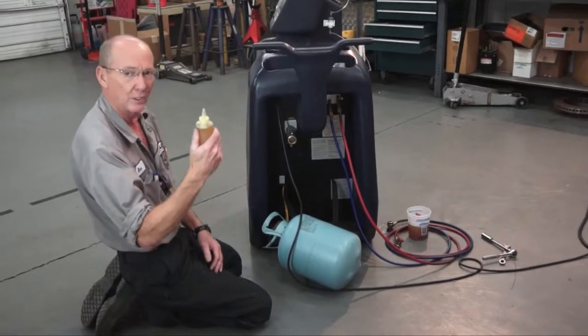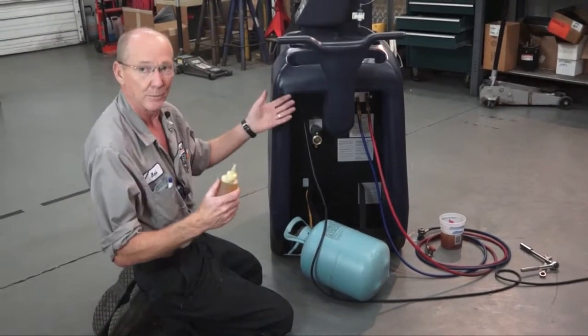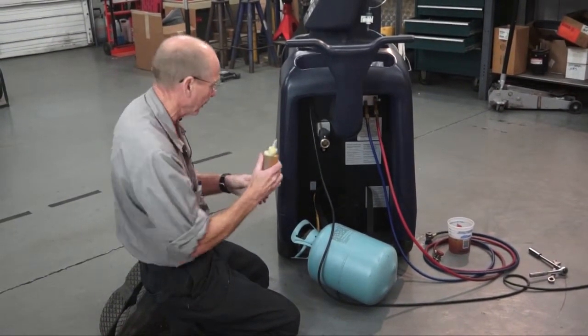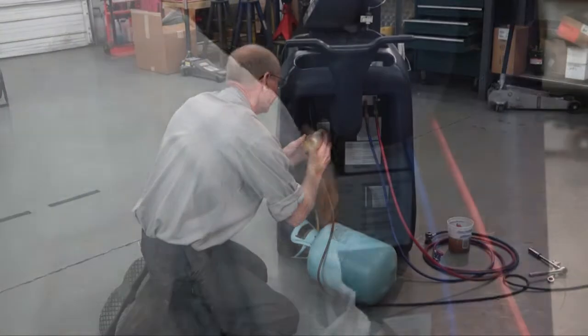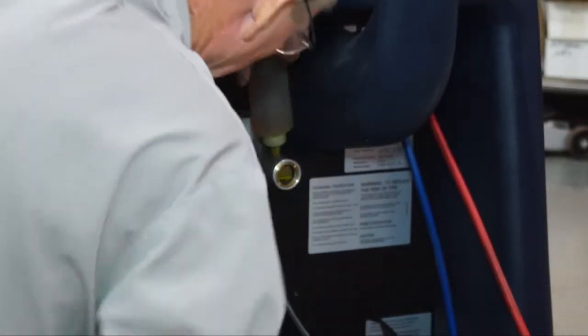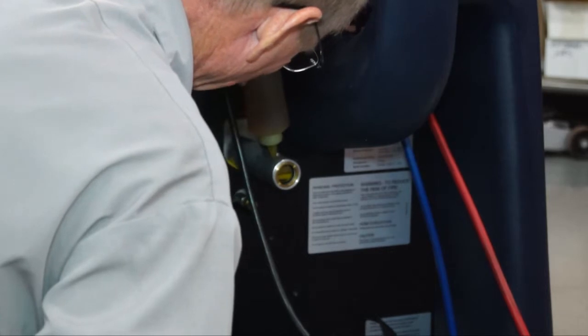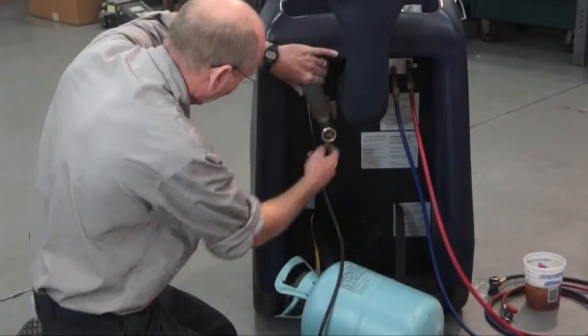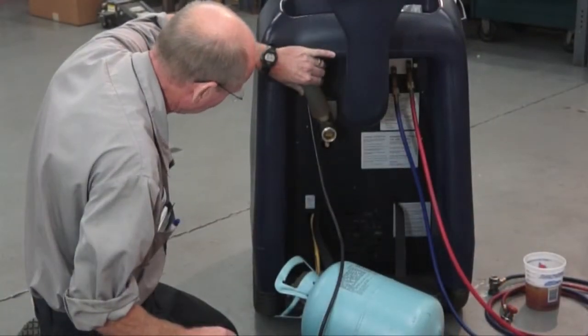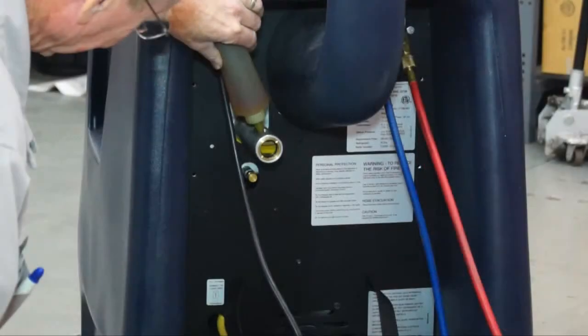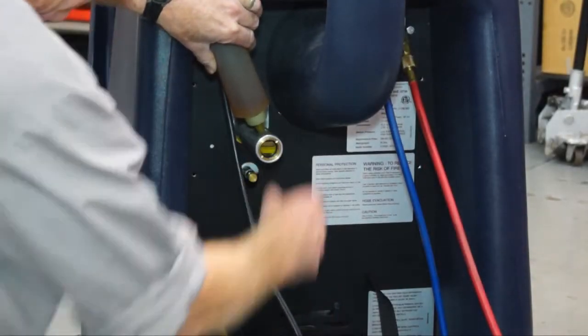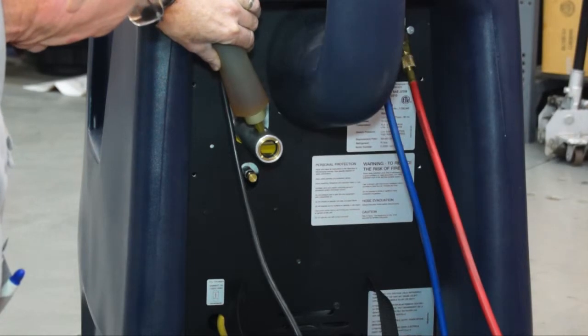And I'll get this full 8 ounce bottle, and I'm not going to run the vacuum pump because there's basically no oil in it, very little oil. So I'm going to squeeze it in just a little at a time. You can watch the sight glass, that way you know you're not going to overflow back out of the hole. But it takes a little bit of time to do that. And you'll know if you're putting too much in because it'll start spilling out the top. It takes a little time to do this.